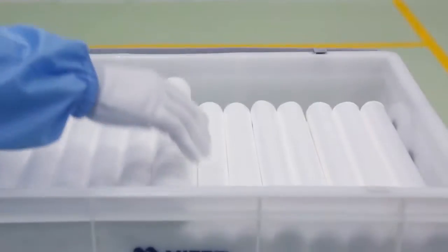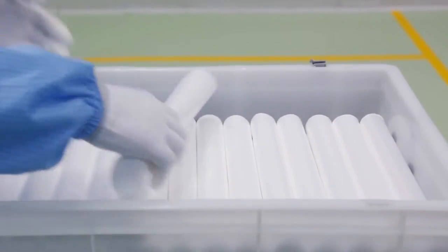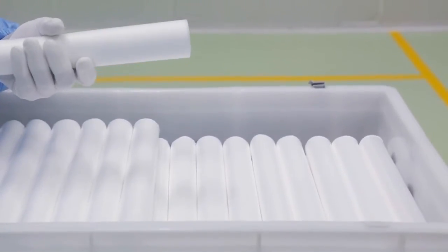The new rippled structure of the membrane fibers makes spacer yarns unnecessary, resulting in a more homogeneous dialysate flow and a smaller dialyzer design. The fibers then pass through horizontal and vertical bars, forming a lattice to form bundles. Bundles are then cut at regular intervals according to the required size.